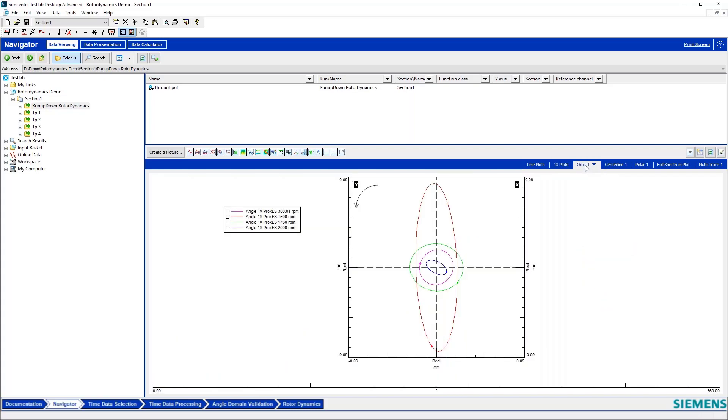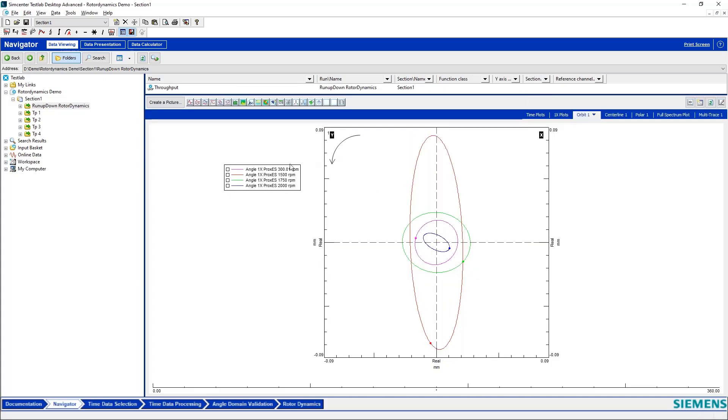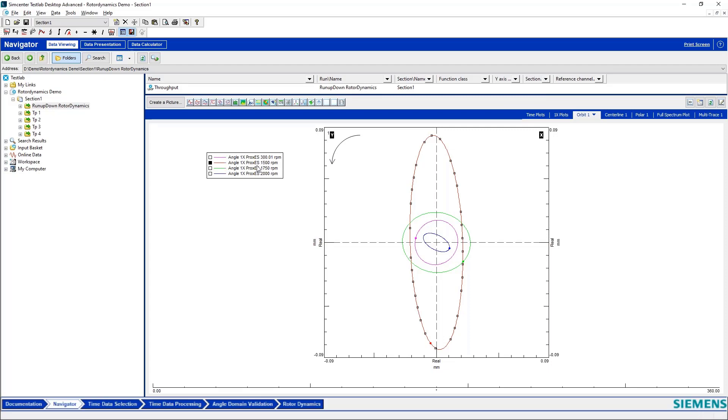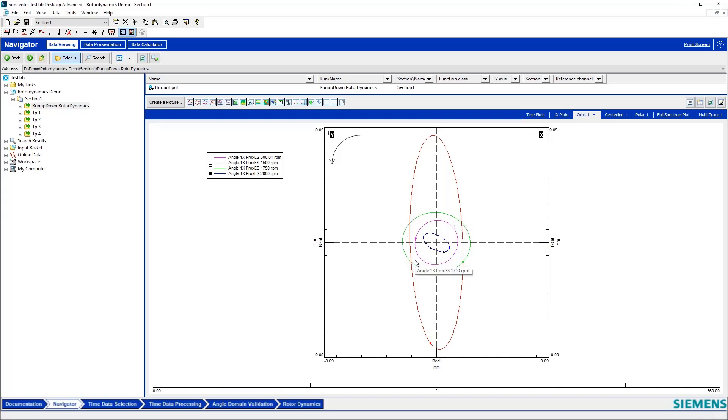I can also look at my orbit plots and what I have plotted here are orbits from different machine rotational speeds. So I've got something plotted from 300 RPM, something plotted from 1500 RPM, something from 1750 RPM and something from 2000 RPM. So these are all showing just one cycle of the machine at that particular rotational speed.